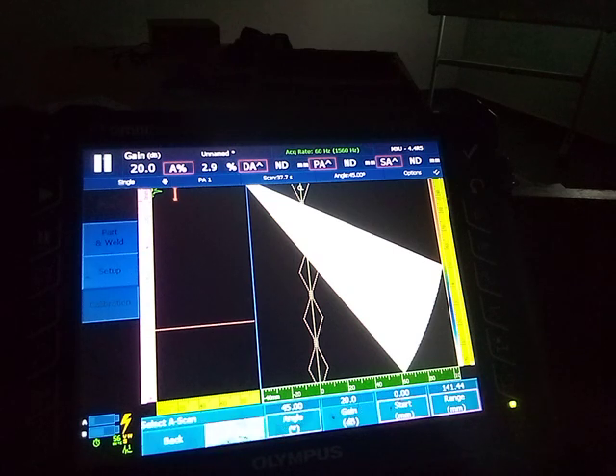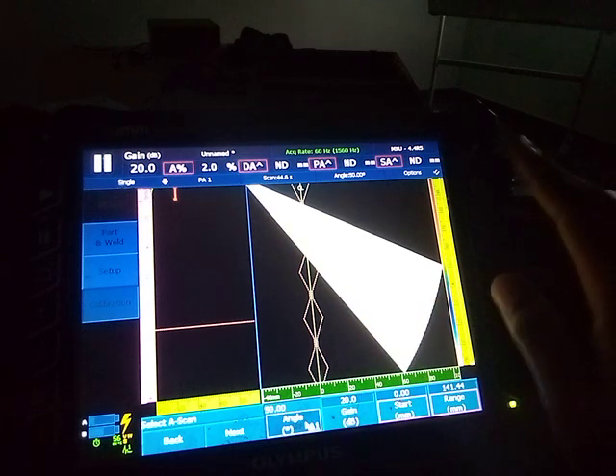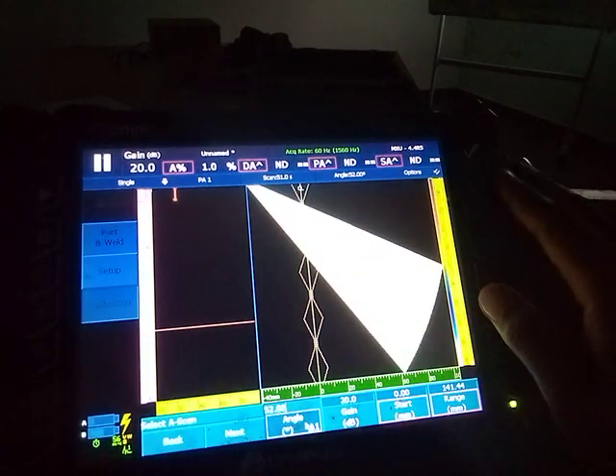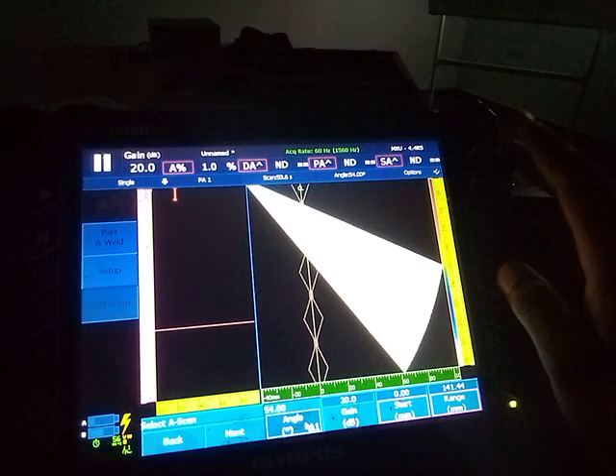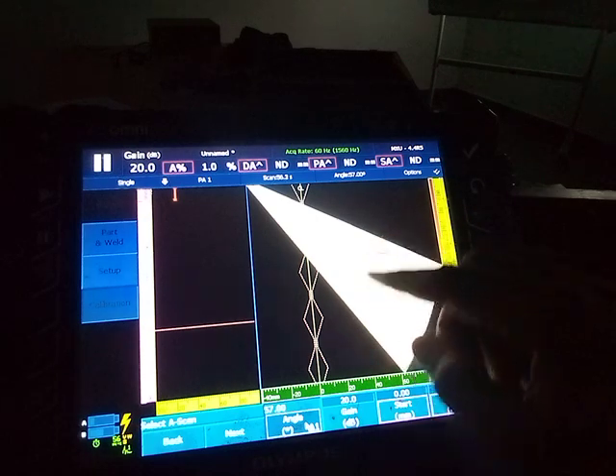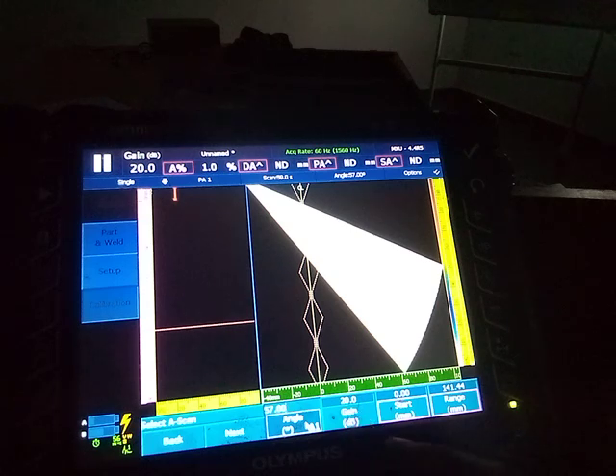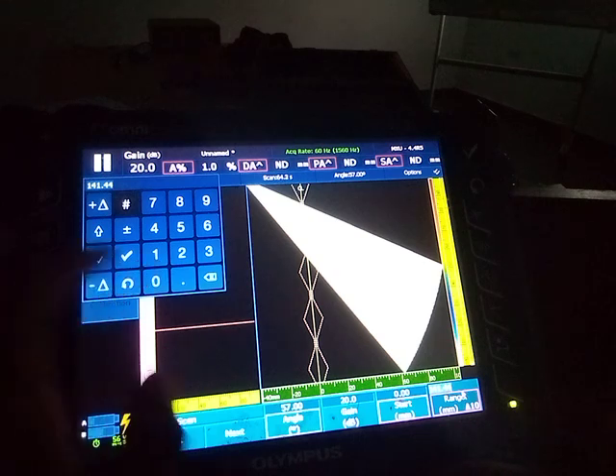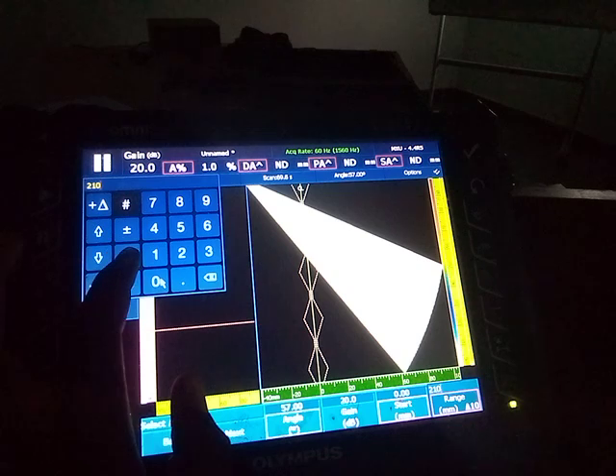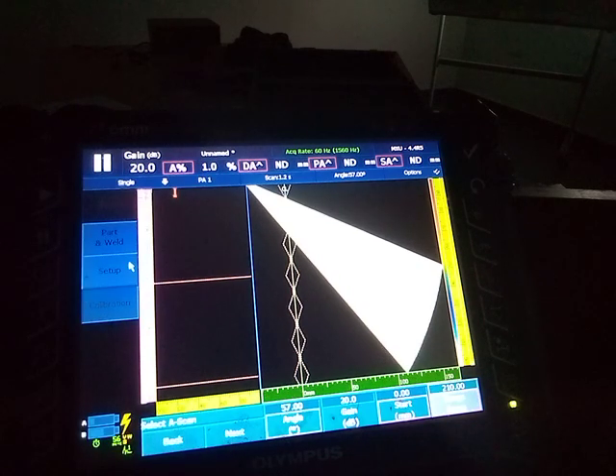So next, the angle. You are going to take any angle, any center angle. Center should be at any angle at the middle. So I'm taking angle 50, let's say 57. What you are doing, you see that your angle is moving. My gain here is okay, my start is okay, my range, since I want to see my second back wall echo, since the second back wall echo is going to be at 200, should be at least 210. Okay, 205 is okay. Then you can see my second back wall echo is appearing.